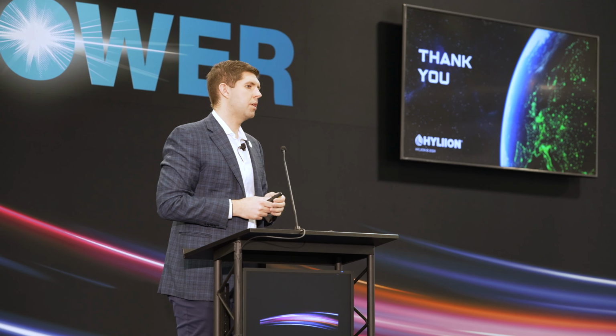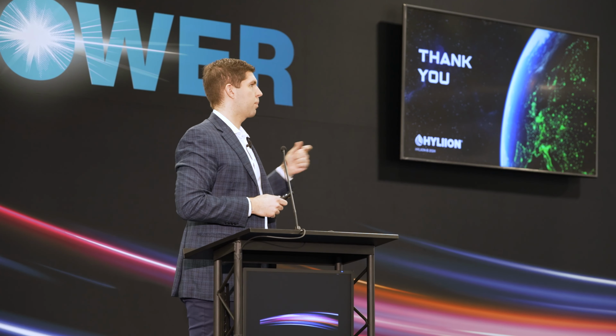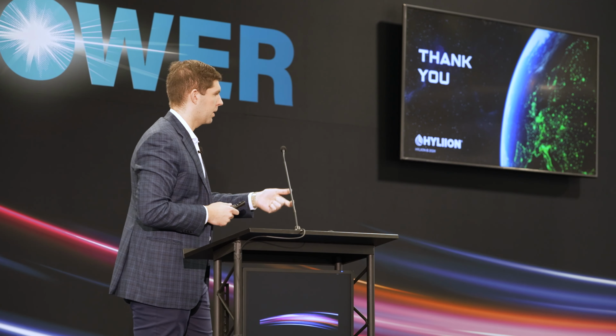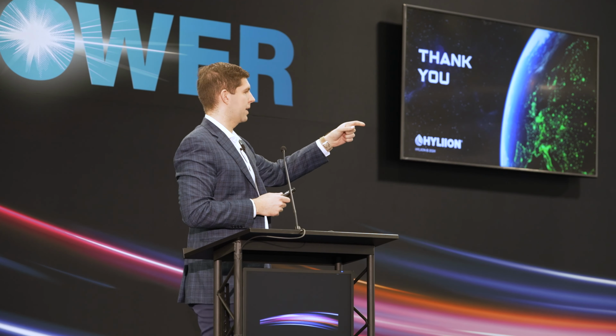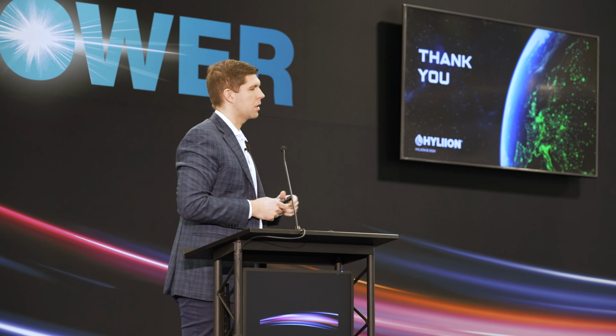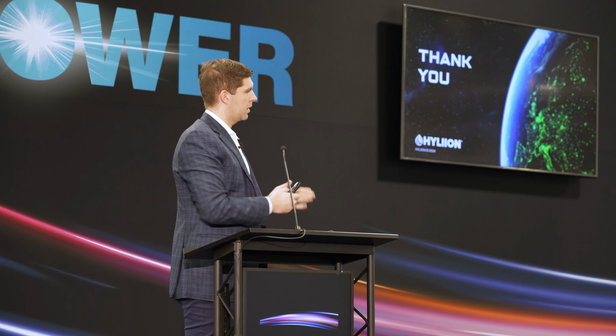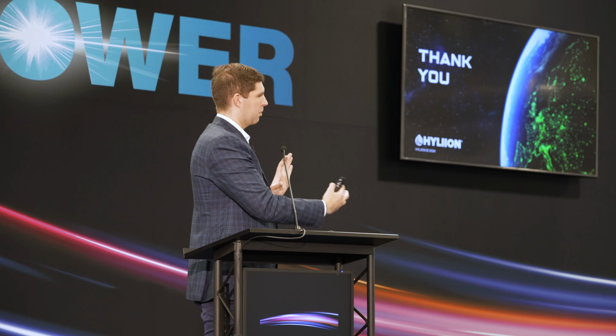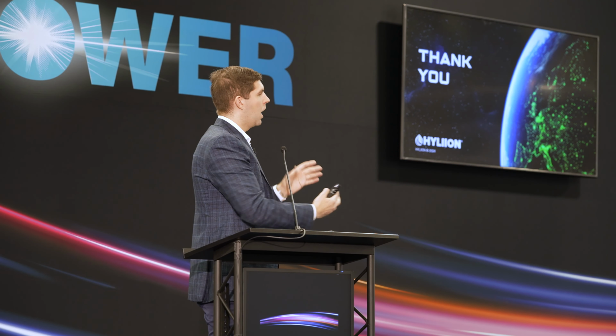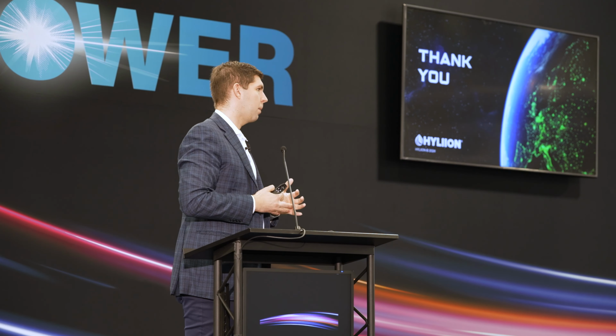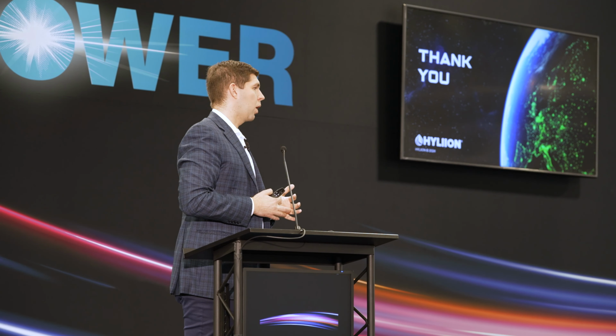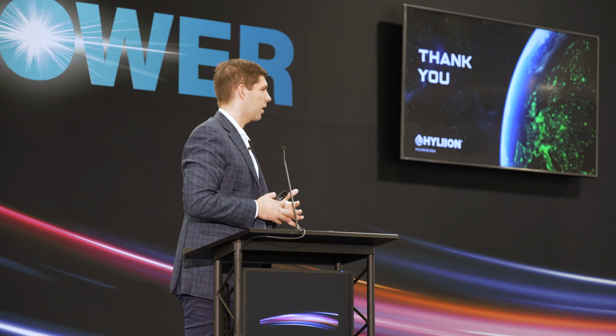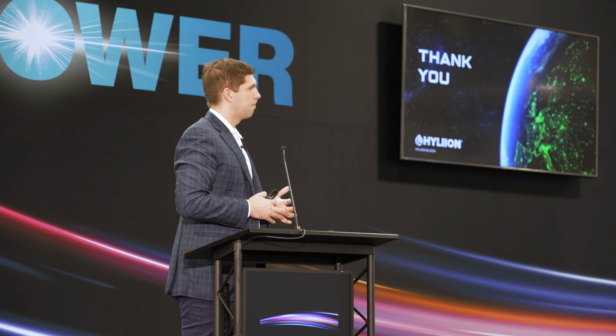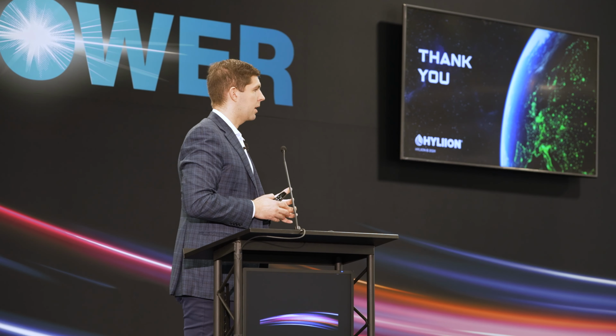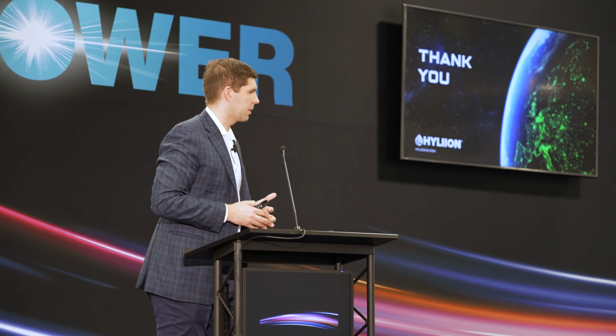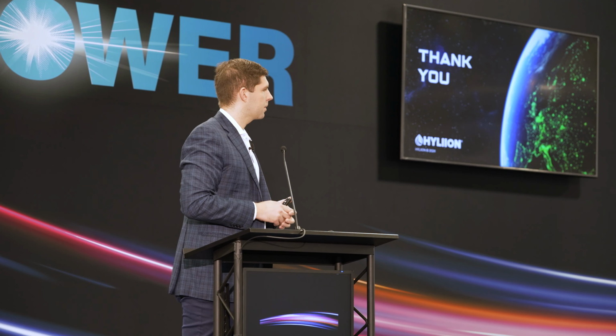In terms of greenhouse gas, if you bring in a fuel like natural gas, that produces CO2 emissions, so your emissions improvement is really driven by the reduction in fuel usage. However, if you look at NOx and CO emissions, since we have that long flameless oxidation process, it's a much longer, cleaner burn of the fuel, so our NOx and CO levels will drop to north of 95% lower than an internal combustion engine's levels. Looking at CARB's emission standards on the NOx end, we will not need any after-treatment system to meet those on natural gas.